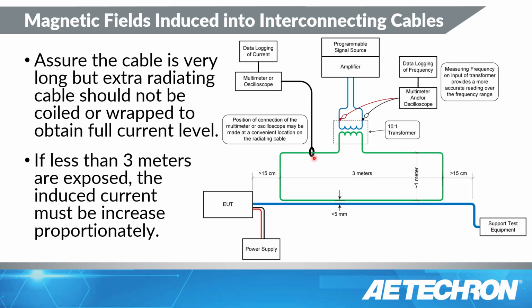You have to monitor how much current and report that at each one of the frequencies that are being tested. And I recommend, if you're going to have to log the frequency, use a multimeter that's capable of frequency measurements. But I tend to put it on the other side of the transformer. The reason why, this is going to be a very low voltage on this side, a very high voltage or higher voltage on this side. The multimeter is going to be able to measure the frequencies easier.